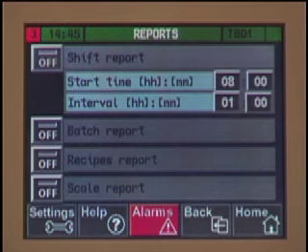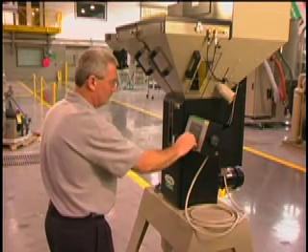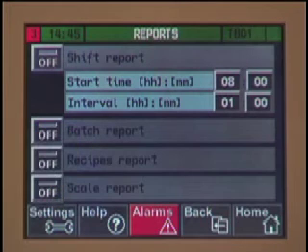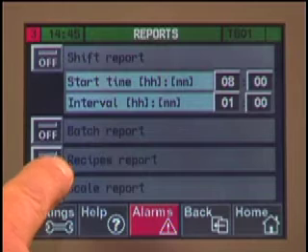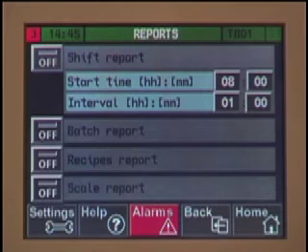Please note these reports are only useful if you have the True Blend reporting software option. The shift report records individual ingredients and total material usage during defined intervals — input the start time and interval time. The batch report shows the average batch parameters of the last three batches at the end of the cycle. The recipe report shows all available recipes including the type of material and the percentages of the various materials. The scale report shows the current measured weight with the current date and time.